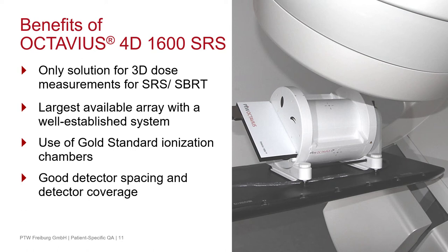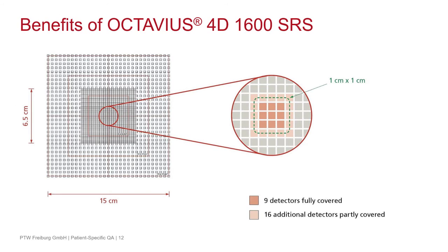For detector spacing and coverage, I want to show you a picture. Here you can see our detector: for a 1 cm² field, you have nine detectors fully covered and 16 additional detectors partly covered — so in total 25 chambers contributing directly to the measurement of a 1 cm² field. The field coverage in the center area is 85%, and there is nearly no space between the single chambers, so there are no blind zones.